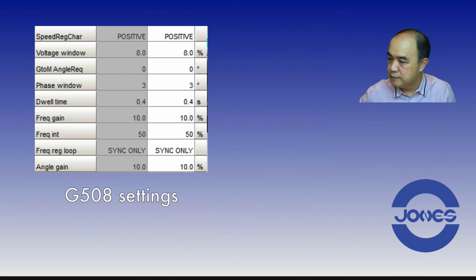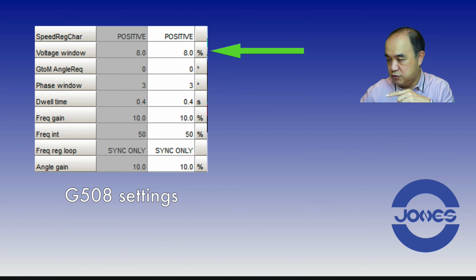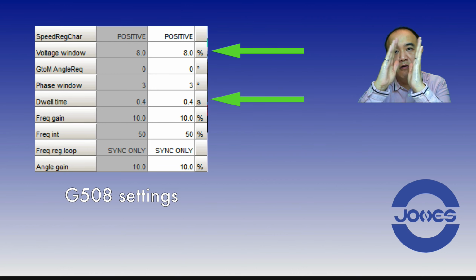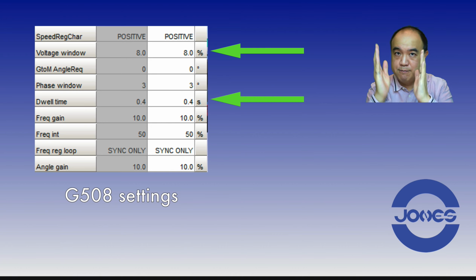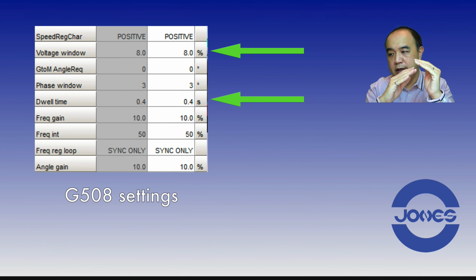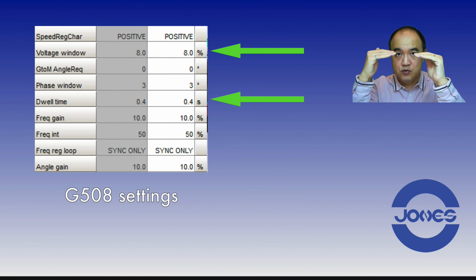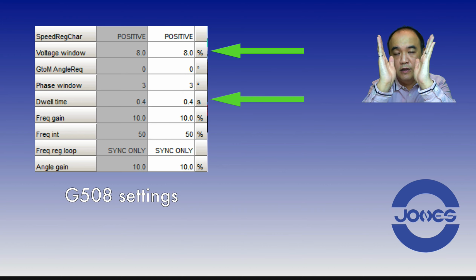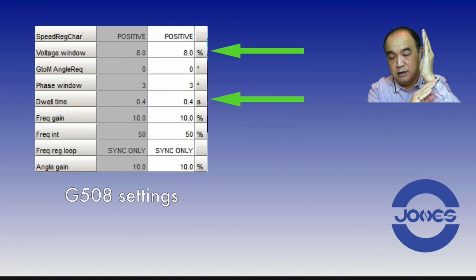So, the original settings that came when they tested the genset at the factory, the interesting points to look at are the voltage window, that's at 8%, which is okay. The dwell time, so this is the time. First off, the voltage window is the window where the two gensets have the same voltage, so 8% difference between the genset voltage. Dwell time is the time when the two sets are in the voltage and the phase window. How long will it have to be inside the window before it sends a breaker closure signal? So the dwell time is 0.4 seconds, which is quite fast.